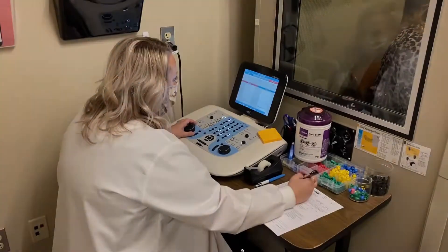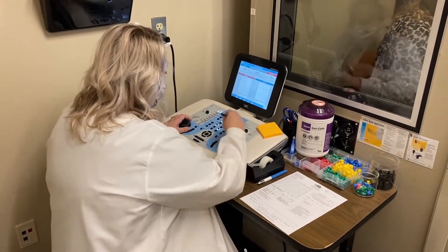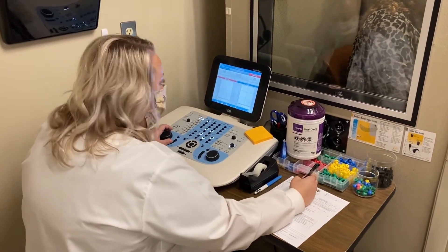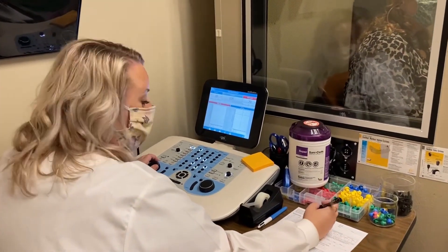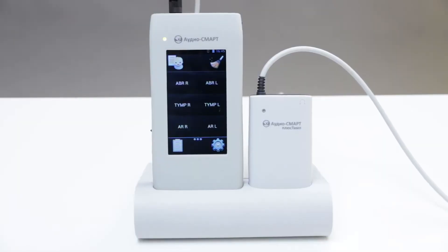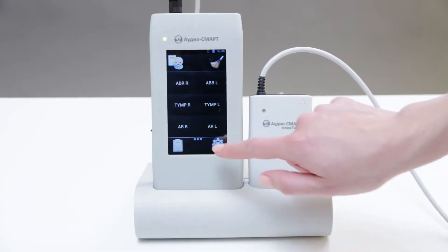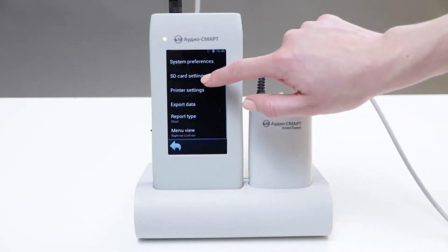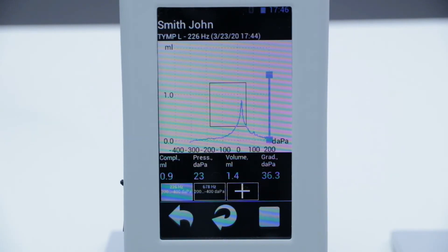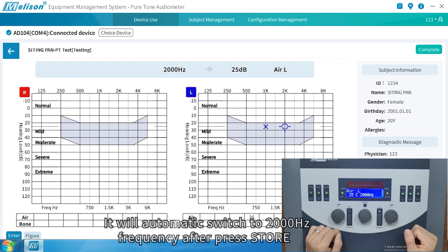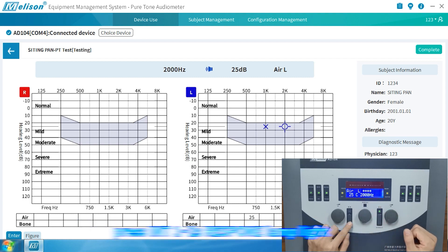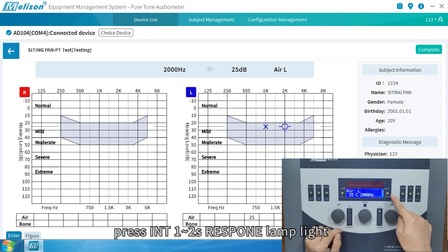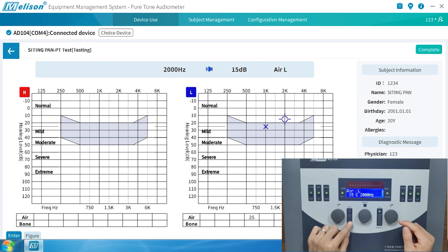Pure tone audiometry is a behavioral test used to measure hearing sensitivity. This measure involves the peripheral and central auditory systems. Pure tone thresholds, or PTTs, indicate the softest sound audible to an individual at least 50% of the time. Hearing sensitivity is plotted on an audiogram, which is a graph displaying intensity as a function of frequency. A basic audiometer should make it possible to perform fundamental audiological tests, determining how much intensity is needed for a patient to hear pure tones at different frequencies. The pure tone audiometer must be able to produce pure tones at certain frequencies, precisely control the levels of these tones, and deliver them to the patient in the manner intended by the audiologist.